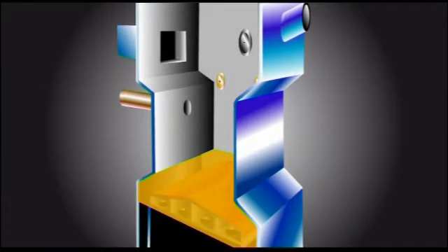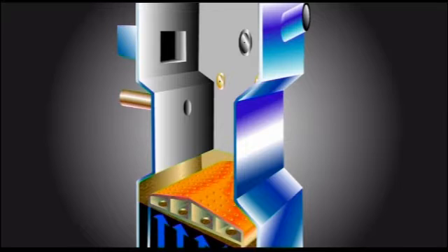The incineration process takes place at a temperature of more than 850 degrees Celsius at the bottom of the furnace. Air nozzles blast primary air through the sand bed. This primary air thrusts the sand bed upwards into the oven.